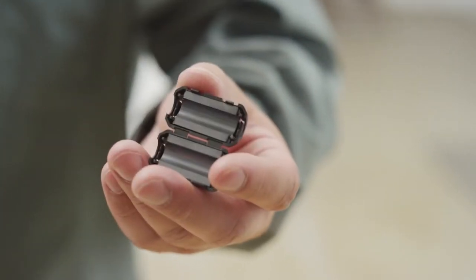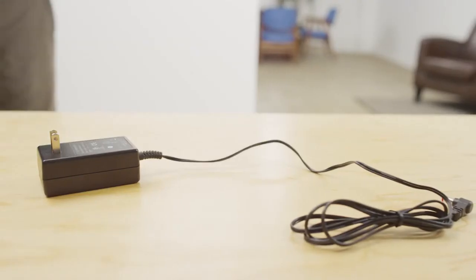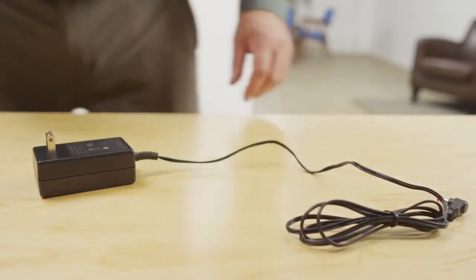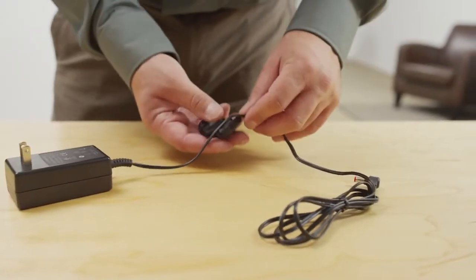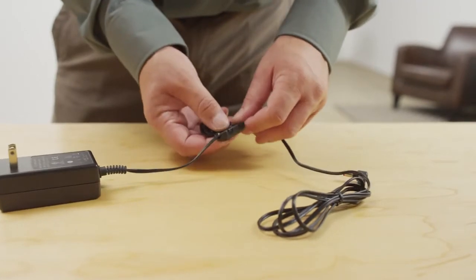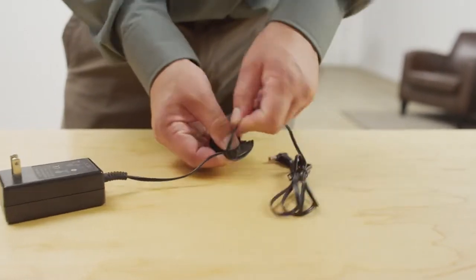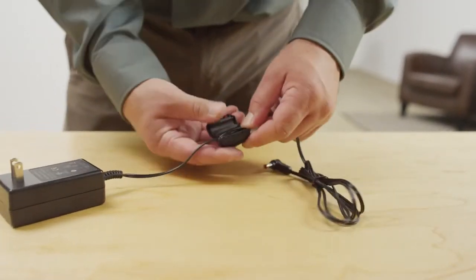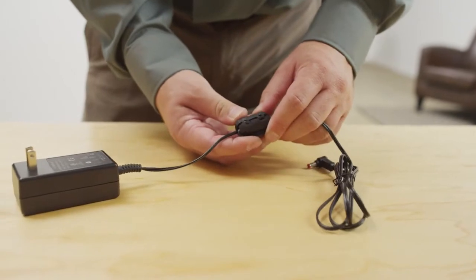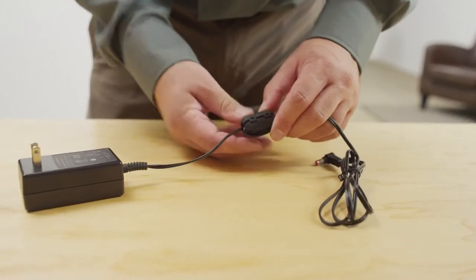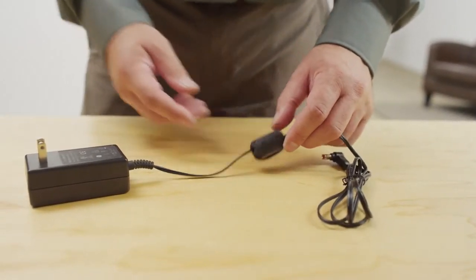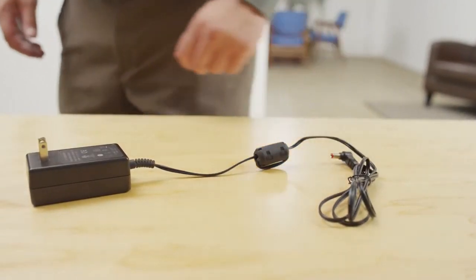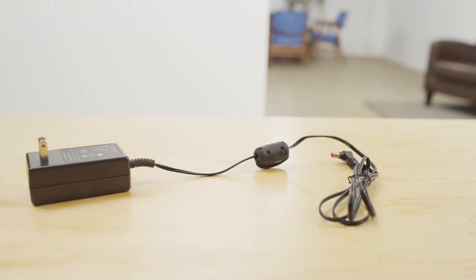The ferrite clip must be attached to the terminal's power cord in order to be FCC compliant. Make a loop in the power cord approximately 6 inches or 15 centimeters from the power supply. The loop will keep the clip from sliding on the power cord. Clamp the ferrite clip over the loop. Make sure the tabs fully engage.